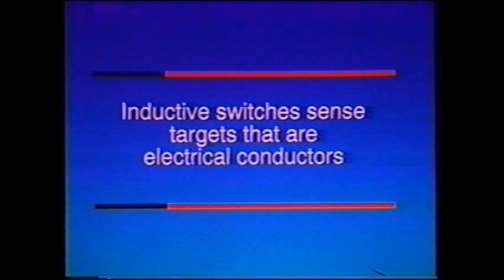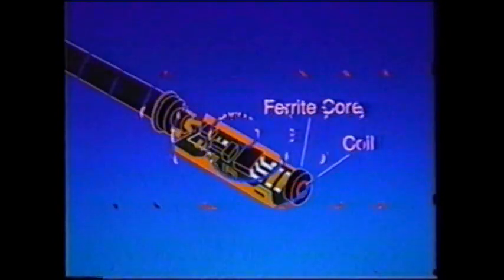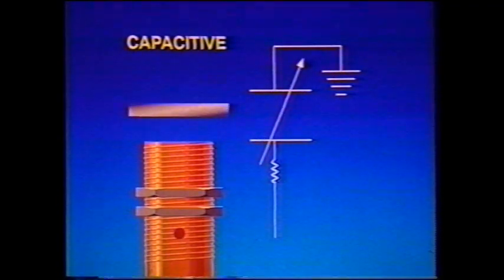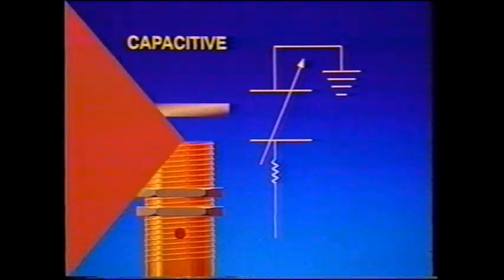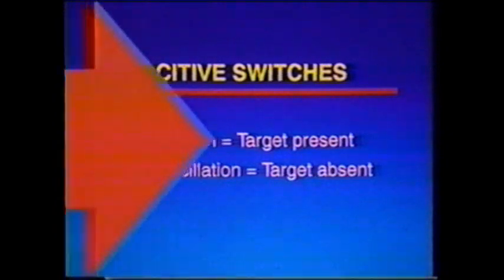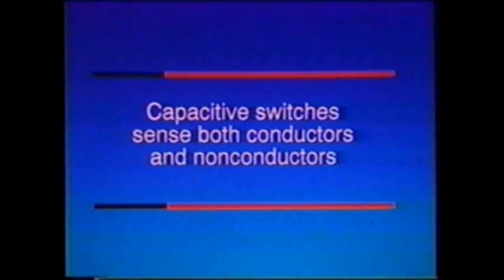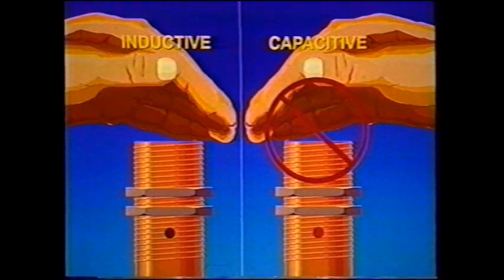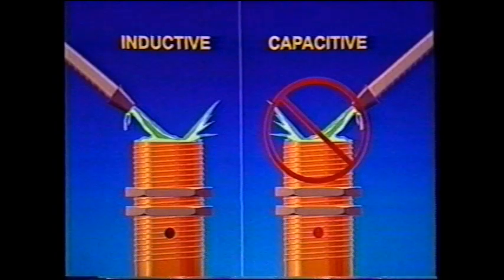A capacitive switch also contains an oscillator, but in this case, the active face of the switch is one plate of a capacitor, and the other plate is ground. When a target enters the active zone, the value of the capacitor changes. When the value of the capacitor is large enough, the circuit begins to oscillate. With a capacitive switch, oscillation occurs when the target is present — exactly the opposite of an inductive switch. Any target which increases capacitance can be sensed, so a capacitive switch can sense both conductors and non-conductors. Never use a capacitive switch when an inductive switch will do the job — you might introduce the chance of a false signal from an operator's hand, cutting fluids, moisture, or dirt buildup.